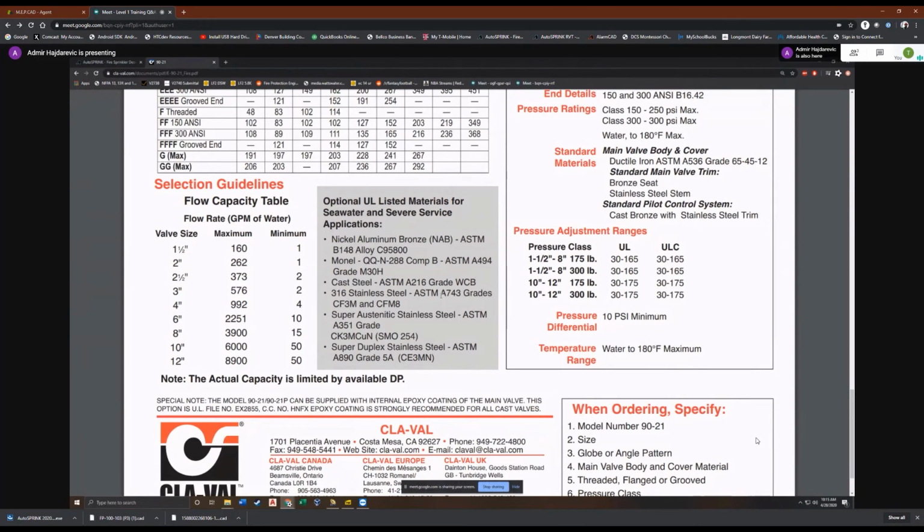Right. I've done that in the past where I didn't want to bother trying to calculate the PRV, so I just made sure that my system demand, for whatever system it was, never exceeded the pressure rating on the PRV. I just made sure that I never had a pressure demand anywhere downstream of my PRV that exceeded that valve setting, 150 or 165 or whatever. Yes, sir. That's basically what I want to do.